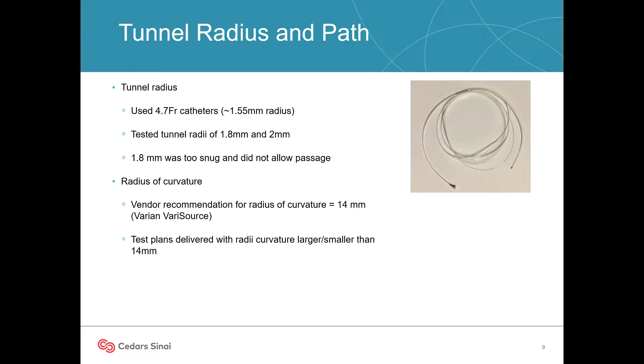The other aspect of the channels that we need to ensure for deliverability is the radius of curvature. So if the curve of a channel path is too tight, then the wire cannot traverse and you'll get a blockage error. So the combination of these 4.7 French catheters and the afterloader that we currently use, which is the Varian VariSource, has a recommended radius of curvature limit of 14 millimeters. So we set that as our threshold, and we tested both larger and smaller radii. And we did find that 14 millimeters was the limit, and anything that was smaller than that, the wire would not traverse and you'd get a blockage. So we set this in our system.